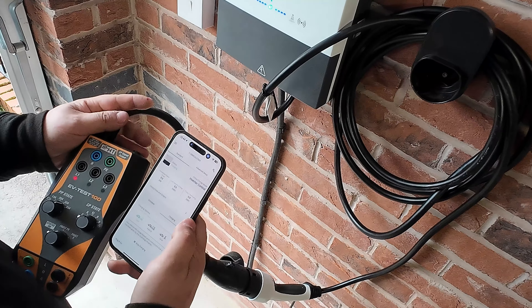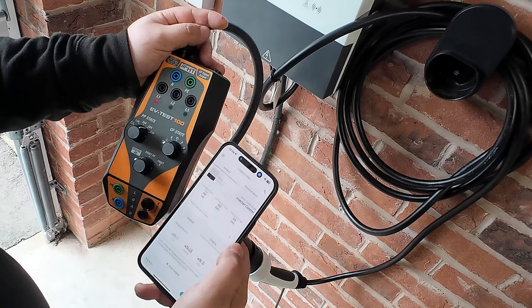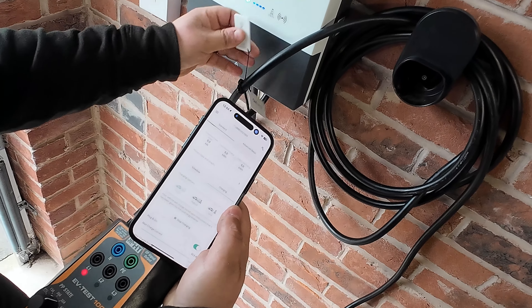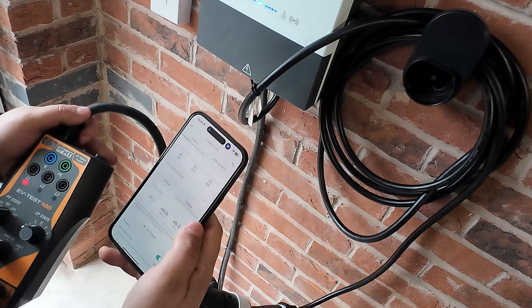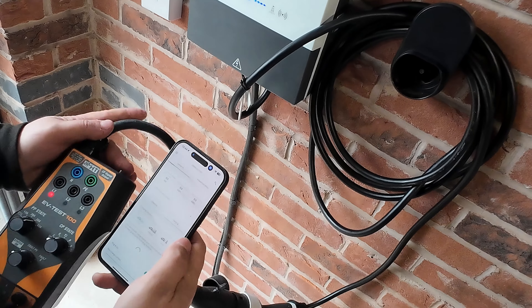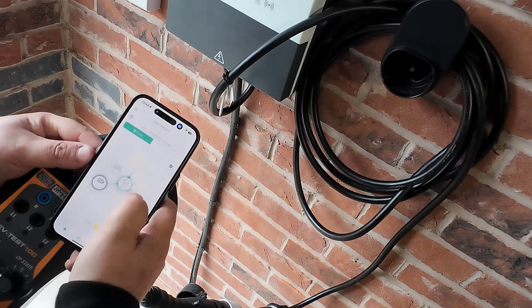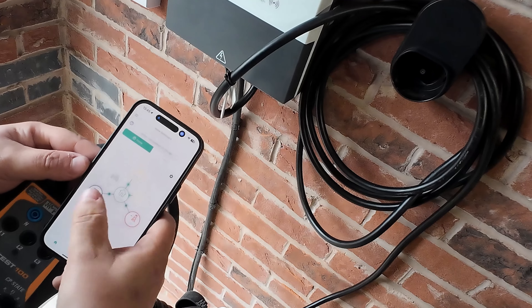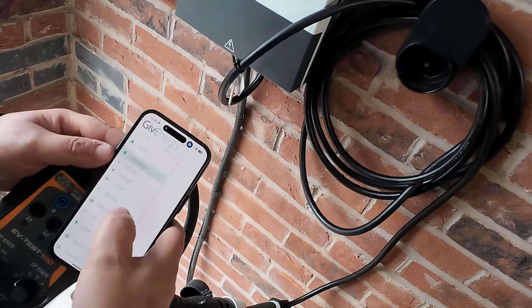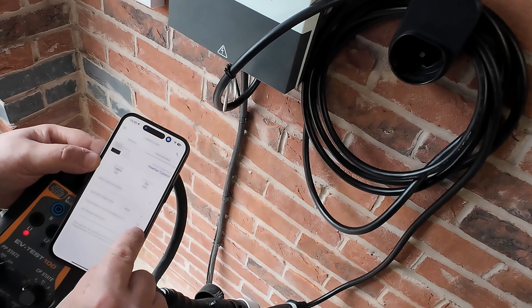We're also bringing a data link cable across because we're in a detached garage and the wireless signal isn't the best, so we want to maintain that connection back to the inverter. Inside there is a GivEnergy five kilowatt hybrid inverter. We need to use the RS485 link — we've got the connector ready to go onto our CAT cable so the inverter and the EVSE charge point can see each other, basically to stop the charger emptying the battery when it's not wanted.